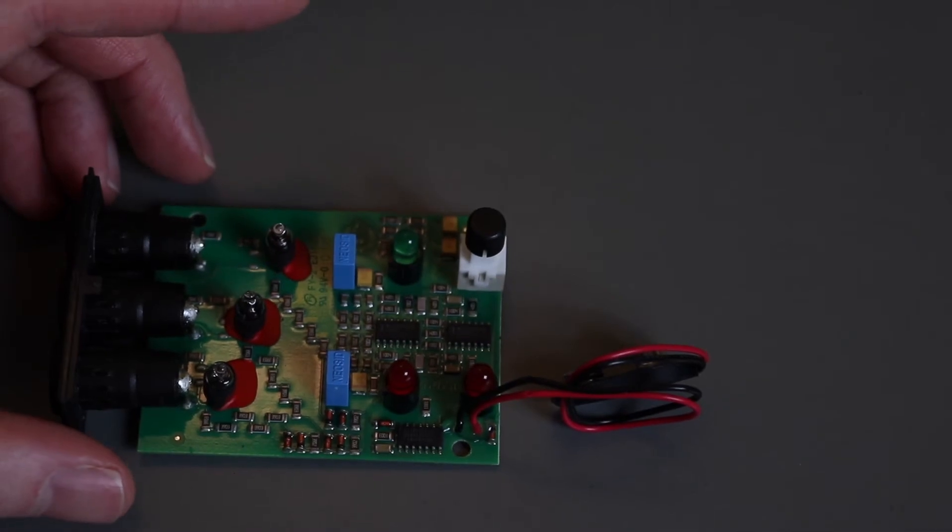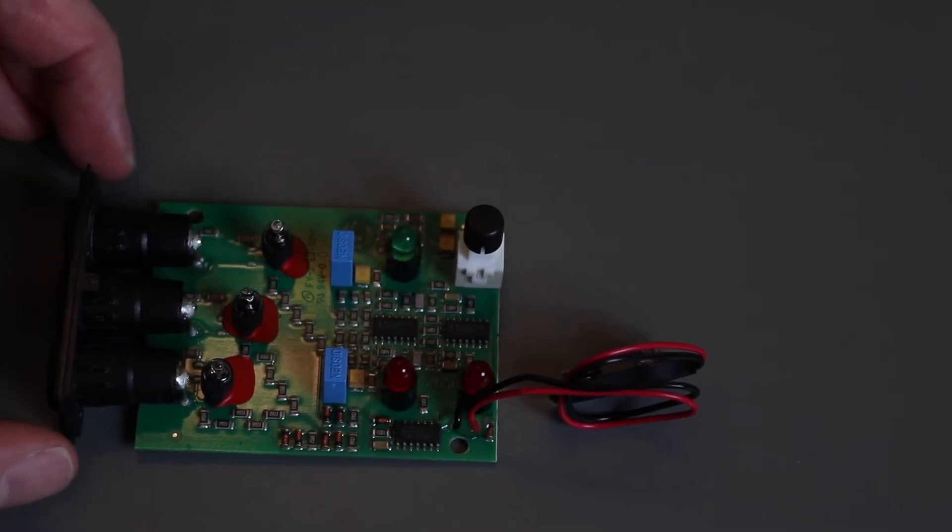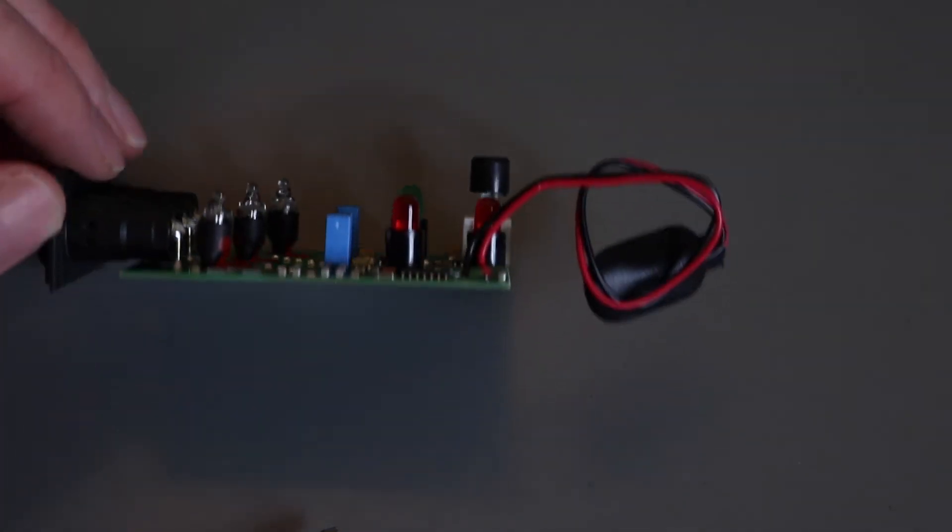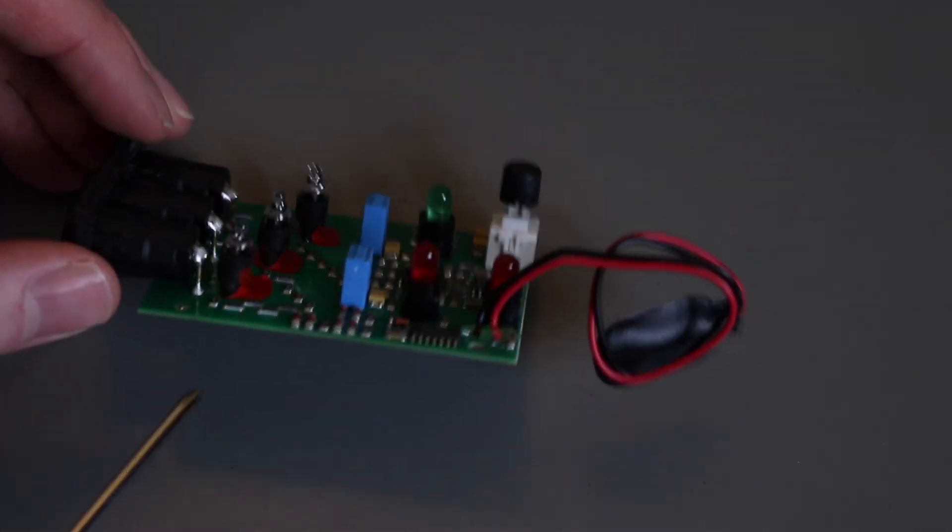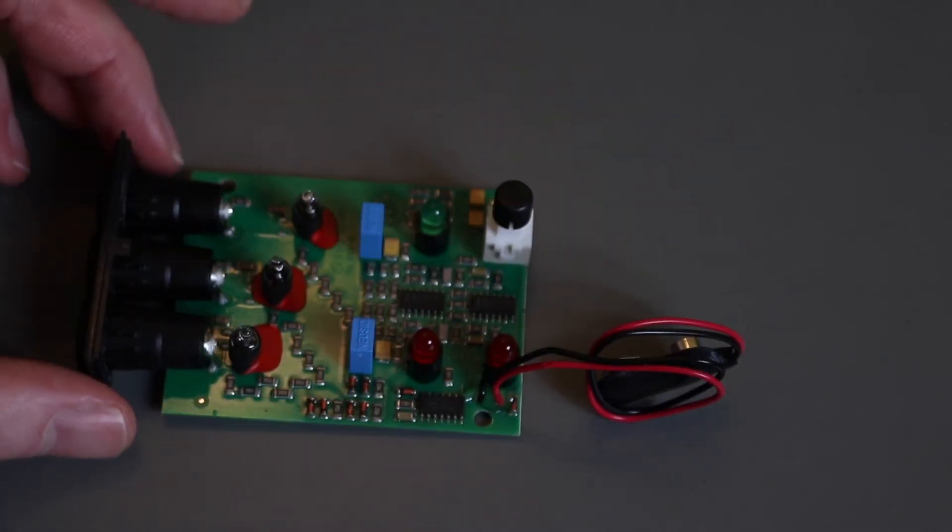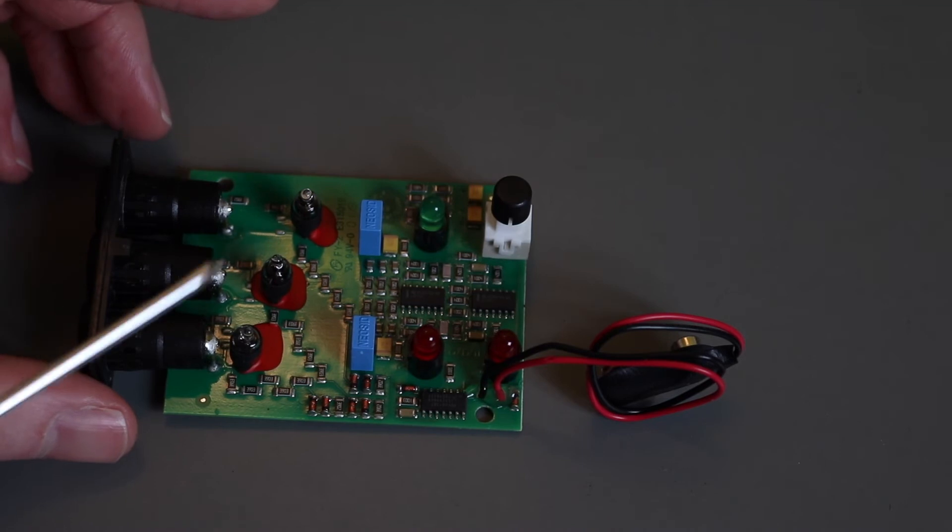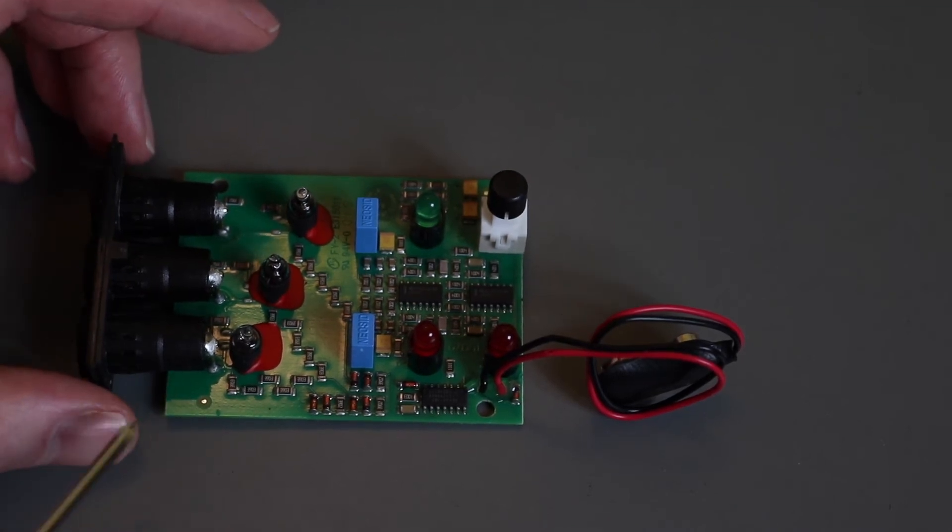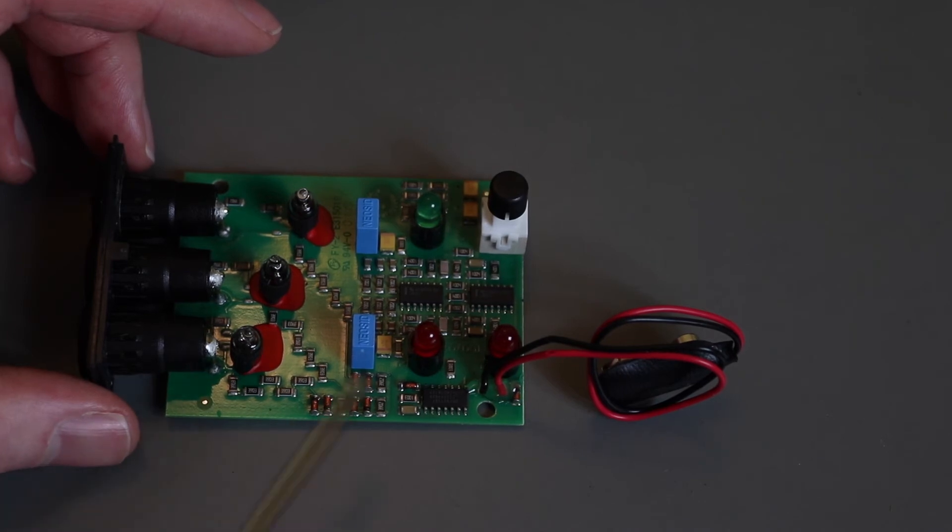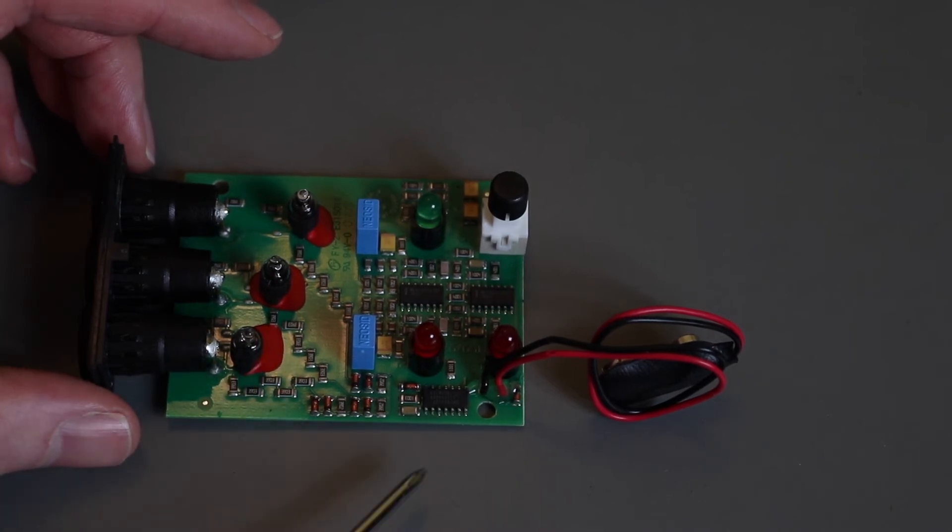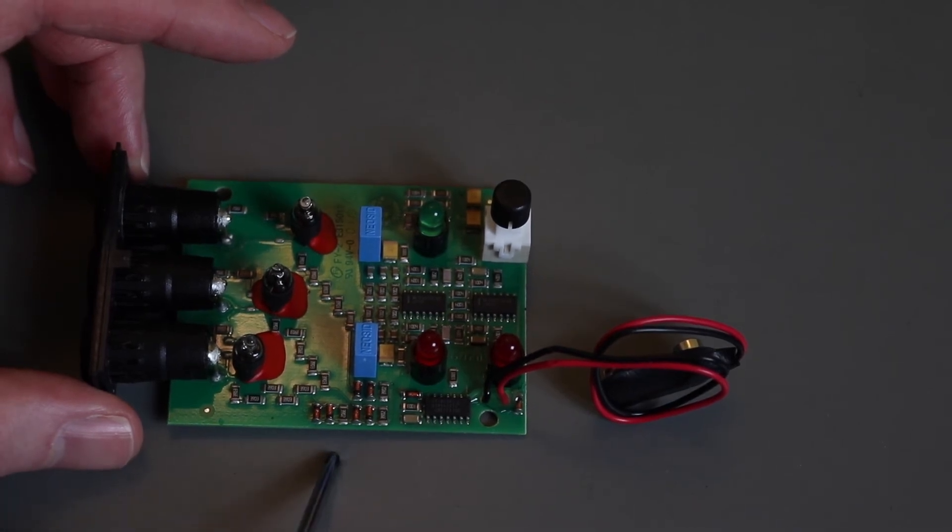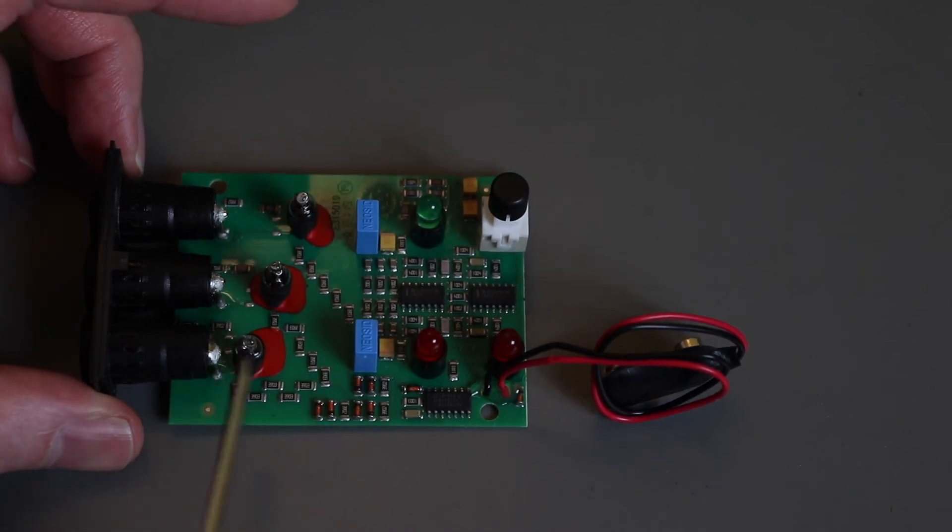This is the Fluke unit. You can see, differently to the Peak meter, the input jacks are soldered directly onto the PCB here, so it's how well the relationship is between the case and the positioning as to how much strain goes onto the PCB. These here are three neons for the phase indication. As with the other unit, this is CAT 3 300 volts. Similar sort of levels of protection - just the dropper circuits for each of the inputs.